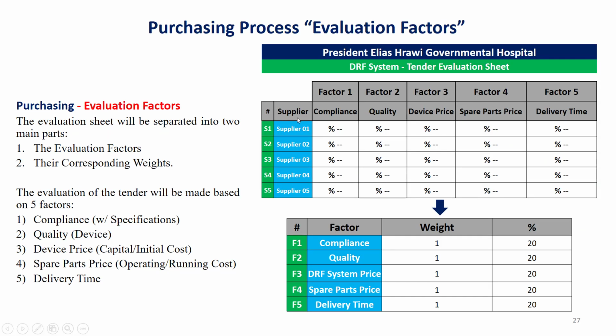The evaluation sheet will be separated into two main parts: the evaluation factors and their corresponding weights. The evaluation factors will be calculated from the comparison summary table, whereas the corresponding weights will be entered by the final decision maker in the purchasing process of this DRF system, which is usually the hospital manager. There are 5 evaluation factors: the compliance with the specification, the quality of the device or system, the price of this device, which is also known as capital or initial cost, the spare parts price, also known as operating or running cost, and the final factor is the delivery time.